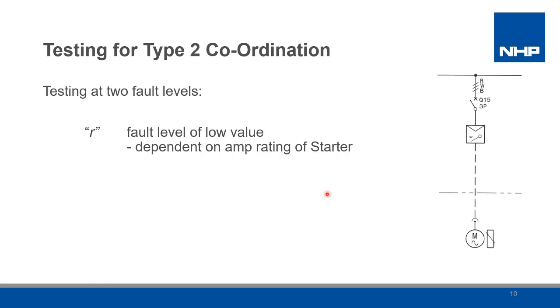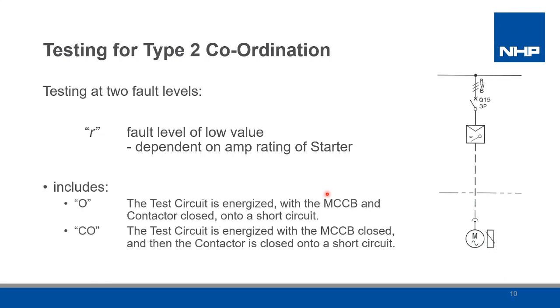For testing of a starter combination, it is verified at two levels. The first is the R value, which varies based on the starter size and is a lower fault level, which would be a real-life incident and is in the region of the instantaneous tripping point of the circuit protective device.